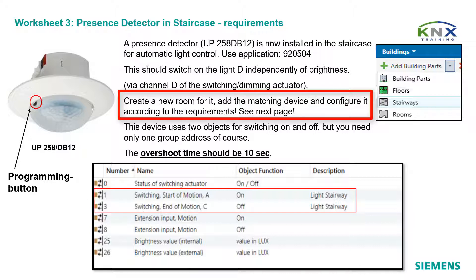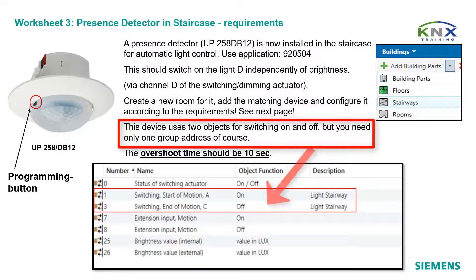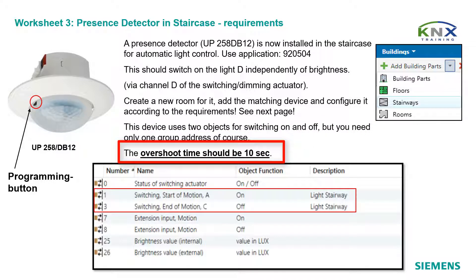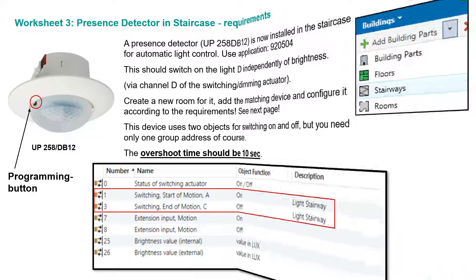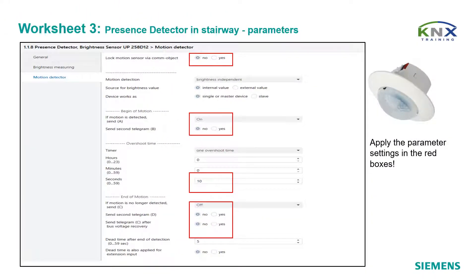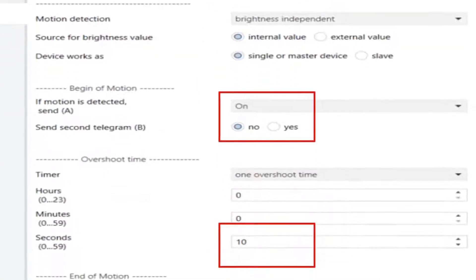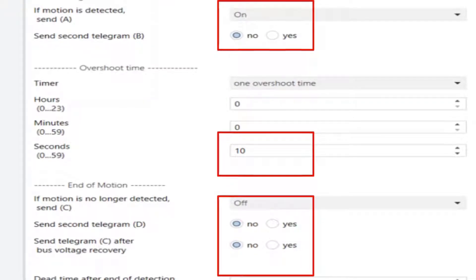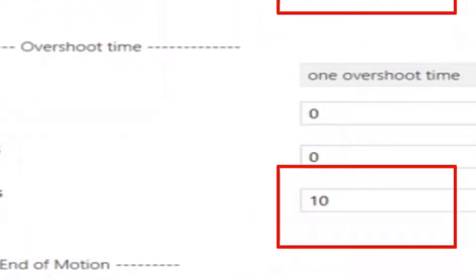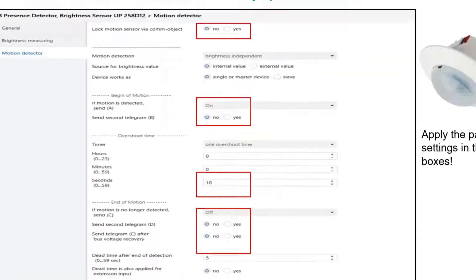Add the matching device and configure it according to the requirement. This presence detector should switch on light D independently of brightness via channel D on the switching dimming actuator. This device uses two objects for switching on and off, but you need only one group address. The overshoot time should be, for practicing only, 10 seconds. Apply the parameter settings in the red boxes: no lock option, settings for begin and end of detection, and the overshoot time of 10 seconds for test purposes.